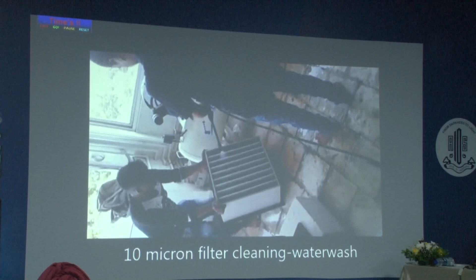This is very important because you really have to monitor how your HVAC system is cleaned. Remember, your 10 micron filter can be water washed because these pores accumulate a lot of dirt. You should not air wash your 10 micron filter. You have to water wash your 10 micron filter. The 3 micron filter should not be water washed. It has to be air washed because if you water wash, the 3 micron filter is damaged. And then the air compressor also has to be cleaned with water. And your terminal HEPA filter should never be cleaned. It can only be changed.